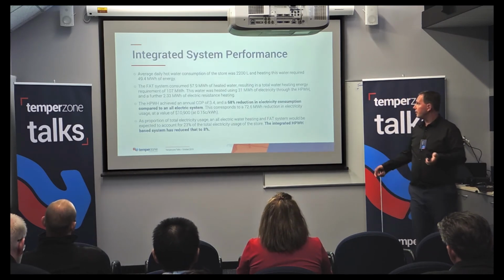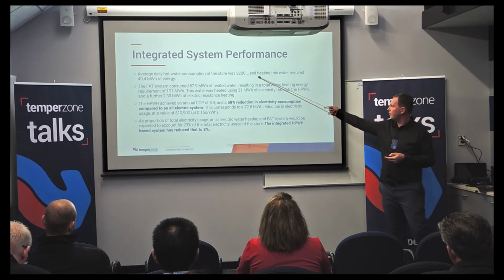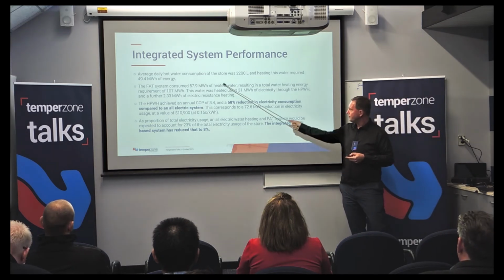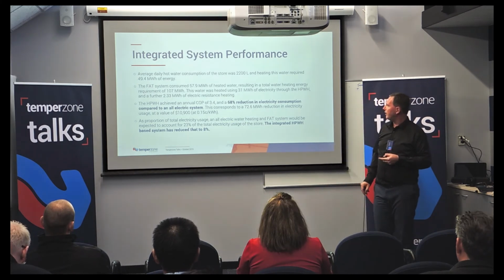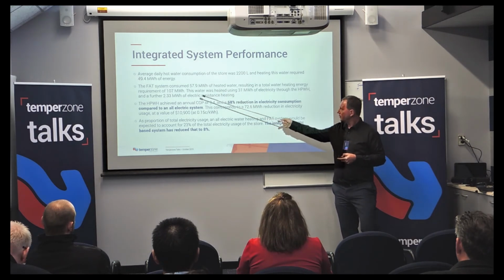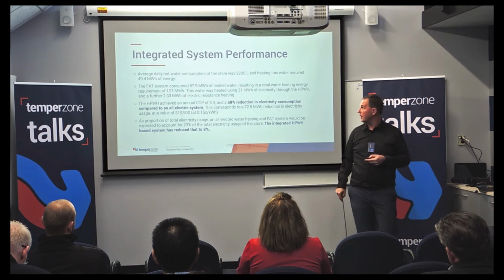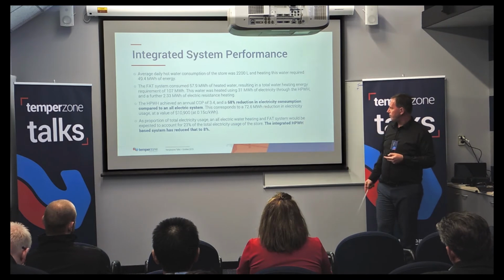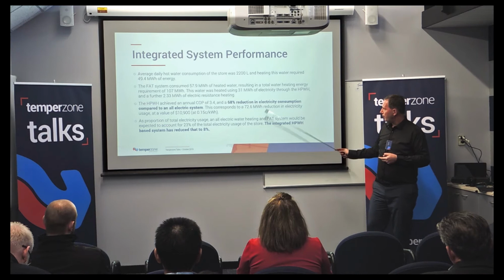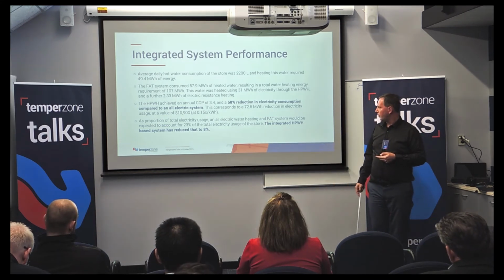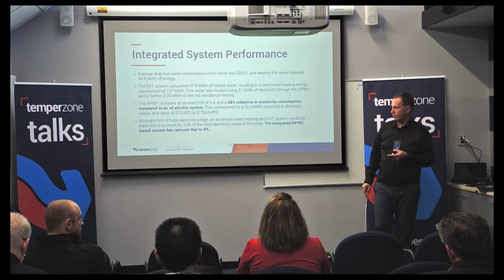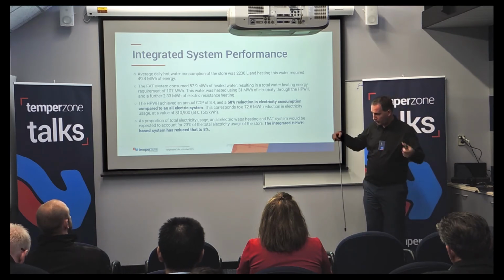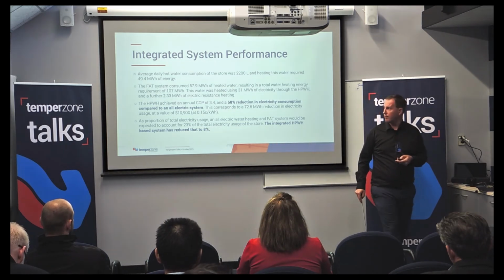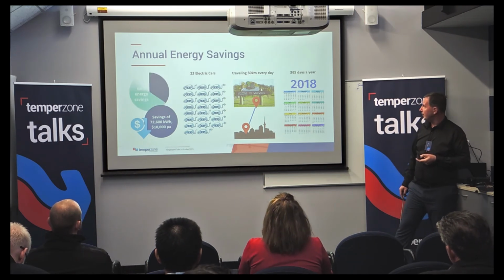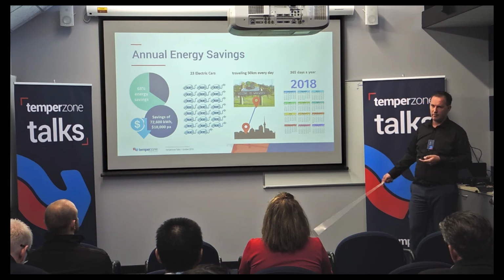So if you look at the performance of the system, the store uses around 2,200 units a day, of which 57 megawatt hours a year was for fresh air tempering. That made up half of what the total store requirement of water heating was, and we achieved a 68% reduction in electricity usage. A seasonal saving in 2024 that was worth about $11,000 at 15 cents per kilowatt hour, and we've reduced the total heating, fresh air tempering and water heating proportion of the store's total energy usage from 23 to 8%, which is the equivalent of 23 electric vehicles driving 50 k's a day each day of the year.